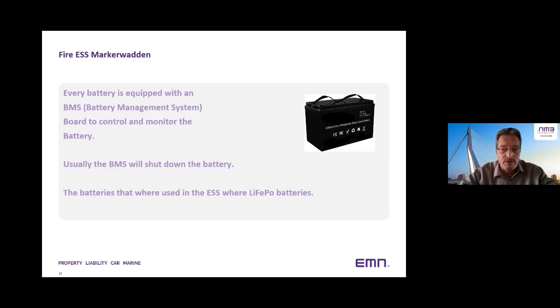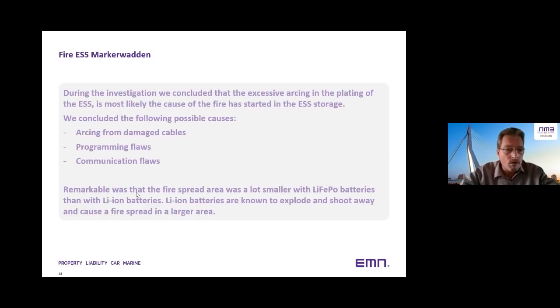That is what we did not find in this specific incident. During the investigation, we did not conclude the exact cause of the short-circuiting that we saw. Possible causes are arcing from the cables, programming flaws because the communication was not well tested, but also installation flaws could be a cause of igniting this fire.